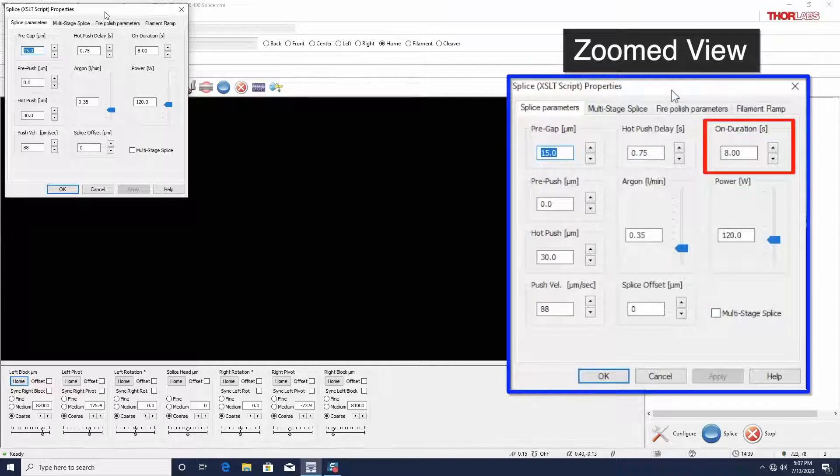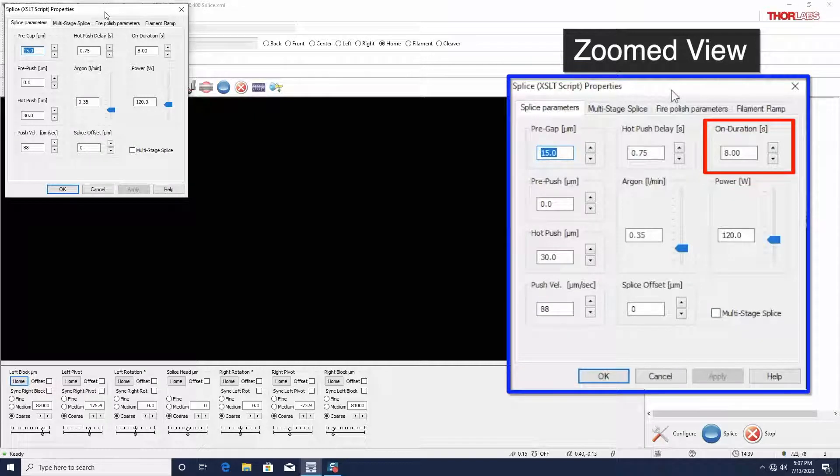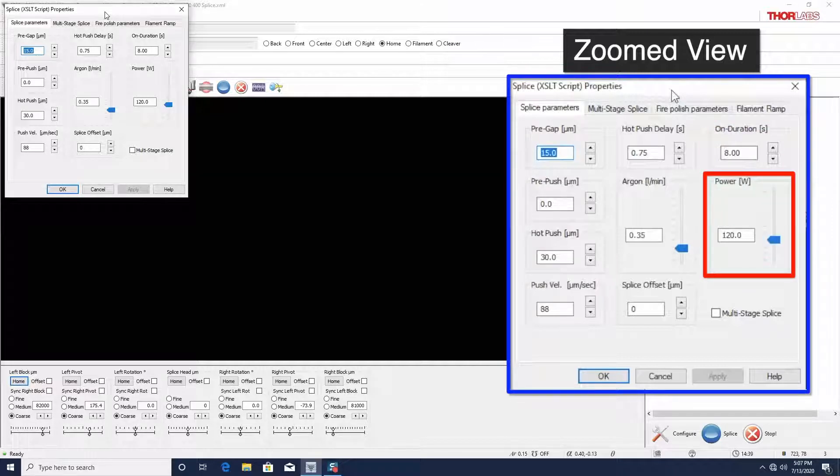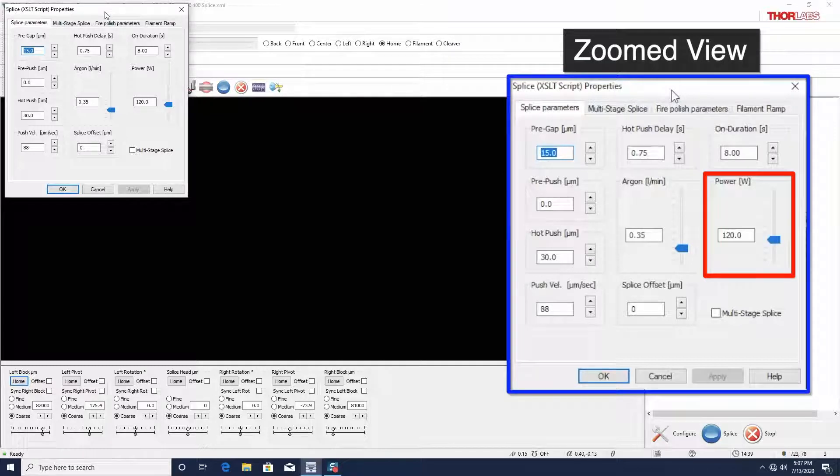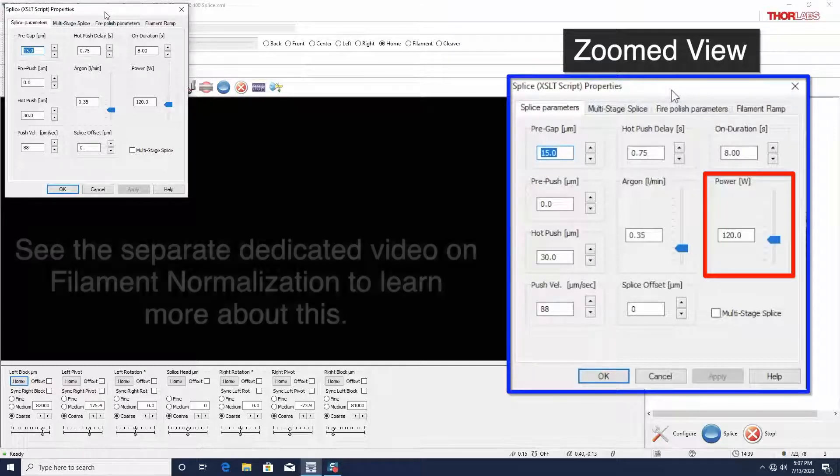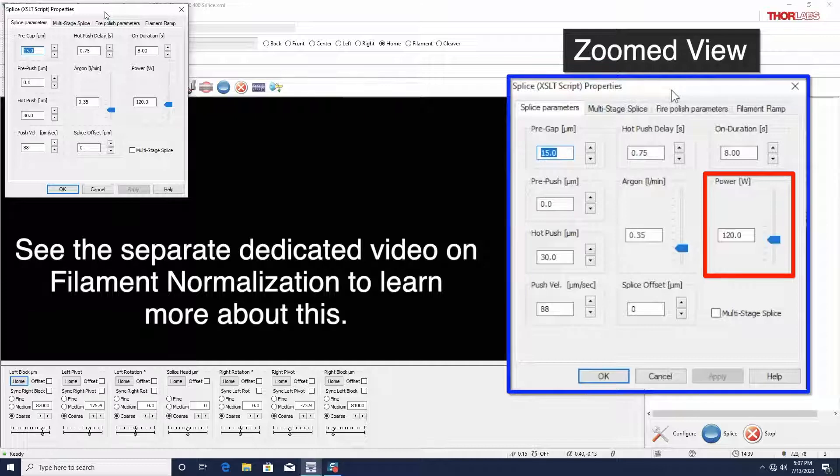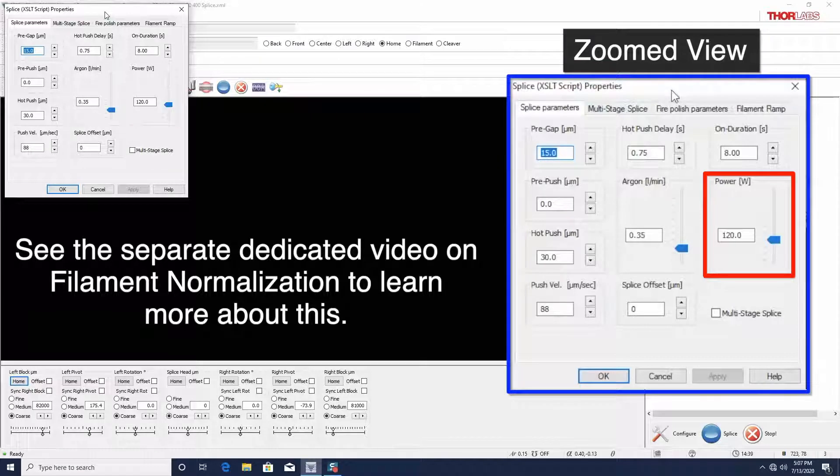On-duration is the time in seconds that the filament will stay at its operating temperature. Power is the nominal electrical power supplied to the filament. Because the thermal response of the filament will change over its lifetime, a filament power offset is added to this nominal value. The filament power offset is determined as a part of the normalization process.